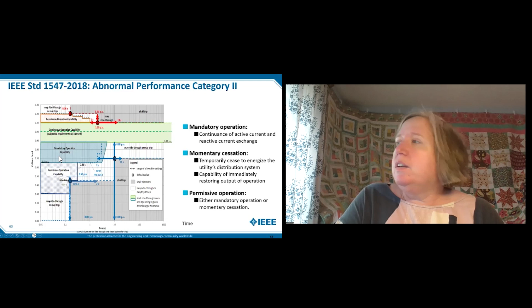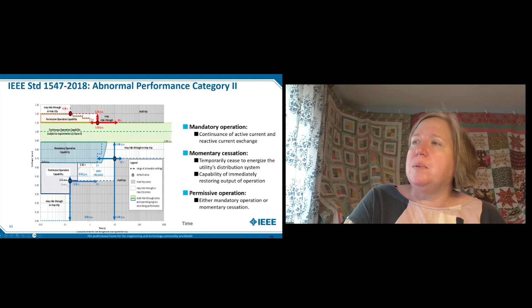So looking at Category 2 in a little more detail, you have the mandatory operation, the momentary cessation, the permissive operation, and you can see these solid lines are where the default trips are. The dotted lines are where you can adjust a little bit, any of the timing and the pickups. But the trip settings are coordinated with the ride-through, so they will not impede the ride-through.